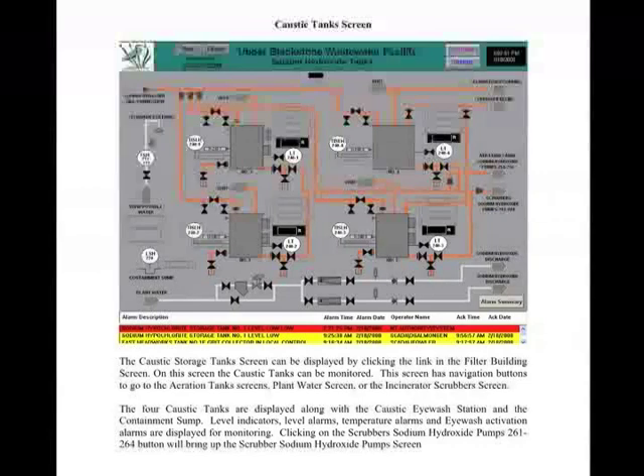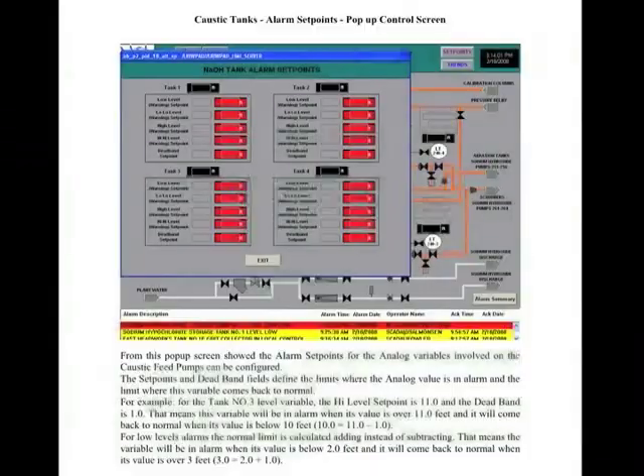There are 6 new caustic pumps for the aeration system that we're not going to get into, but they are fed by these same 4 tanks. We have a total of 4 caustic pumps for the incinerator building. Currently we have 3, it's being upgraded to 4. If you are on the caustic tank screen, you'll have the ability to go from the caustic tanks to either the incinerator caustic pumps or the aeration tank caustic pumps. We're going to actually go through the alarm set points first.